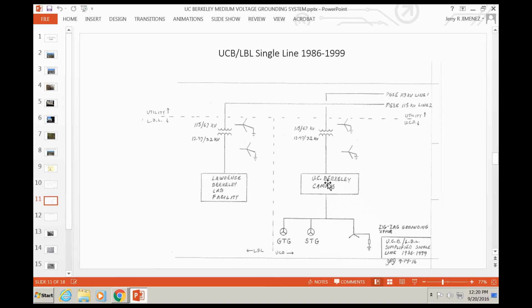Also important to this, the combined output of these two generators could be up to 30 megawatts. In 1986, when this was built, campus load was about 22 to 25 megawatts. So the thought was that if the transformer ever failed or if the utility failed, we would run the campus on these two generators. If the utility failed, we would lose this transformer. We would be separated from it by a breaker that's not shown here. So we have to have some kind of grounding, and that's another reason why we needed some sort of grounding for these generators. Have to account for the situation where the utility's gone and we're running on our own. So obviously we need to have some kind of grounding.